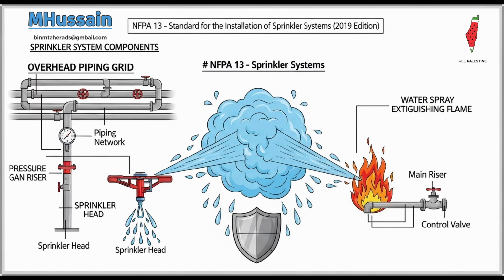Okay, next up, we have a more visual structural concept that profoundly impacts sprinkler placement. Obstructed versus unobstructed construction. And this isn't just a general description, right? It's a technical classification. Oh, absolutely. This distinction is crucial because obstructions, well, they create water-throw shadows, and they can interfere with the upward flow of heat, delaying sprinkler activation. So obstructed construction is defined as structural elements like beams, trusses, or bar joists that materially affect the flow of heat to the sprinkler head or the water distribution from the deflector.